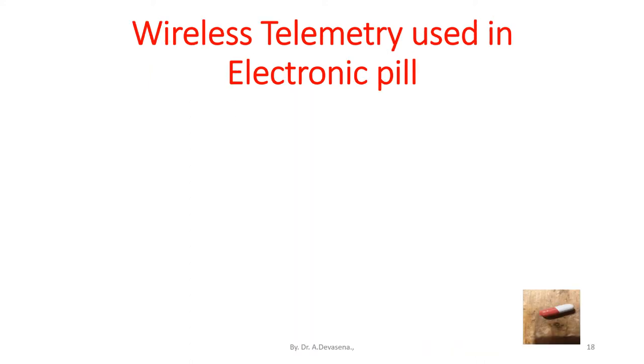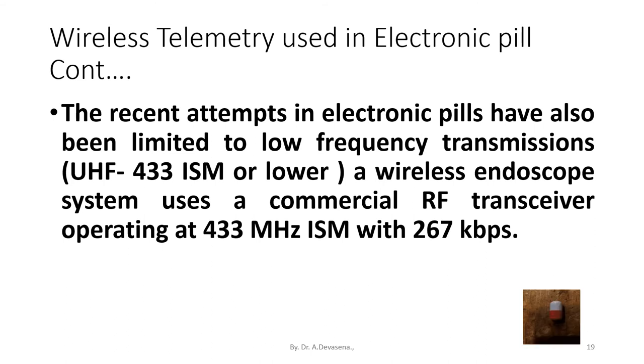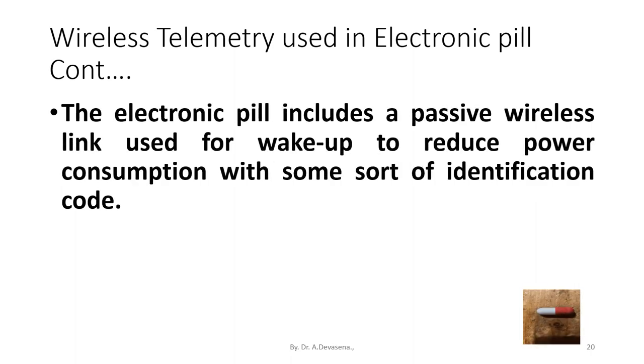Wireless telemetry is used in the electronic pill. The electronic device should be deeply placed inside the body, which makes wireless communication interesting due to its surrounding medium. Recent attempts in electronic pills have been limited to low frequency transmissions, i.e., UHF 433 ISM or lower. A wireless endoscope system uses a commercial RF transceiver operating at 433 MHz ISM with 267 kbps. The electronic pill includes a passive wireless link used for wake-up to reduce power consumption with some sort of identification code.